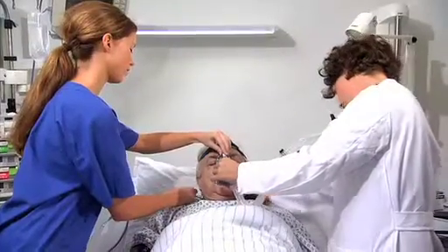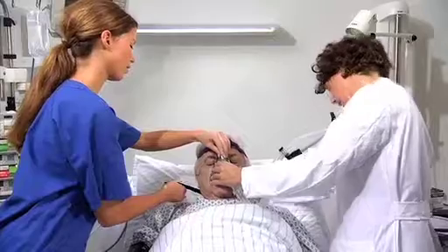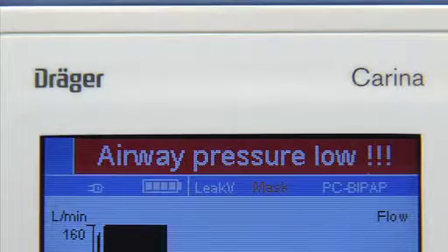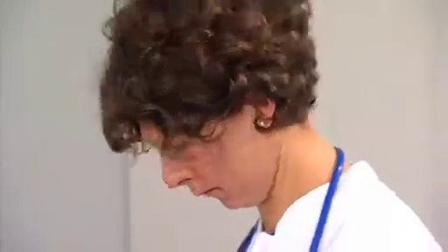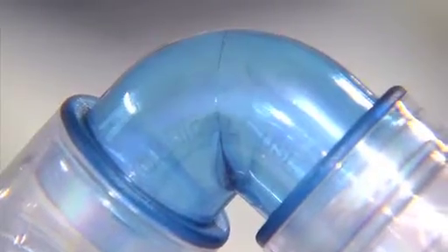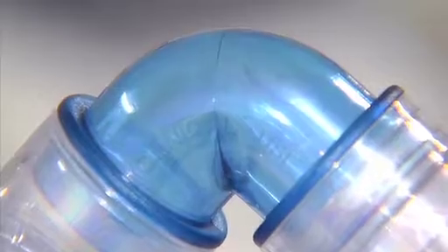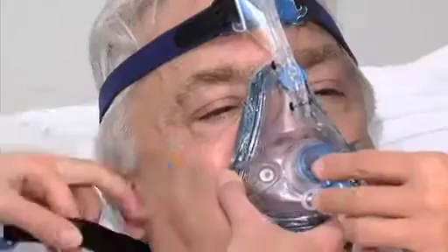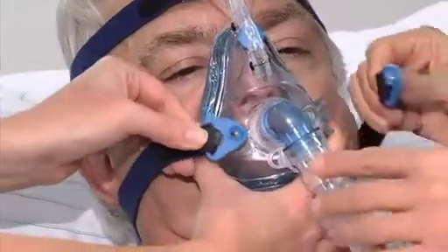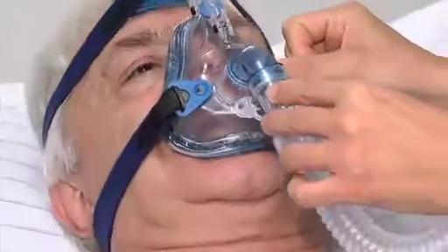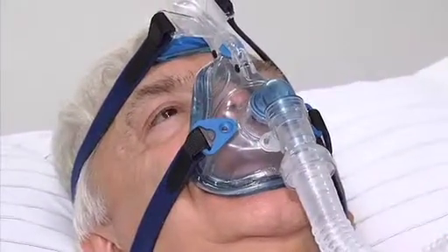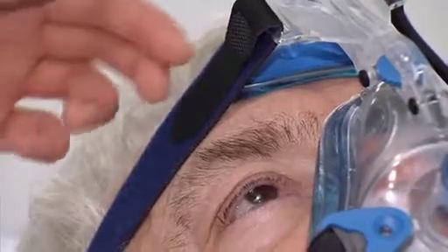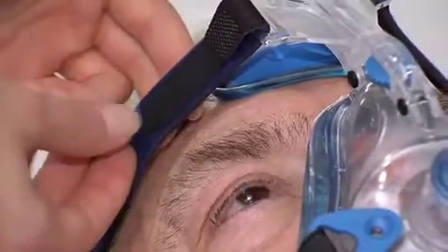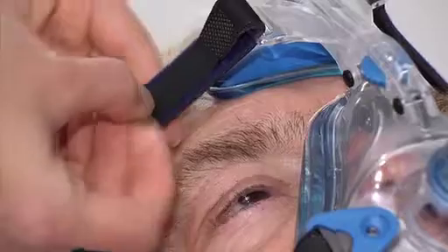While the mask is being adjusted, the airway pressure low alarm may occur. This is due to high leakages caused by movement of the mask. Carina automatically resumes ventilation when breathing is recognized. They attach the two magnetic clips on both sides of the mask. Now they adjust the mask to the center of the face. Unlock the Velcro tabs and pull the strap to tighten it.